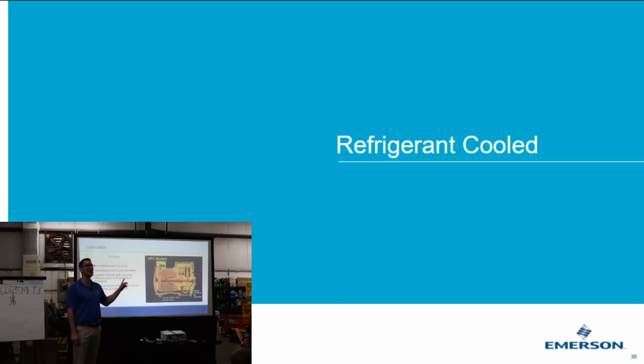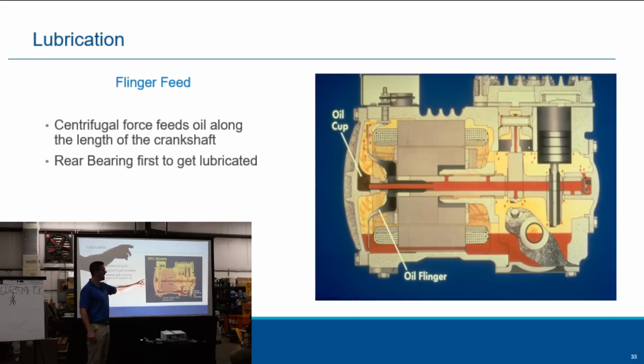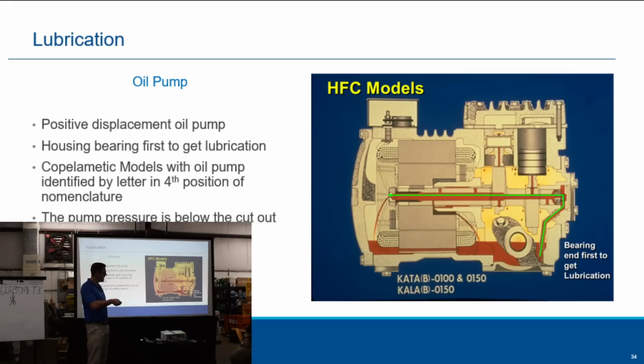What I've seen many times, because I've done tons of teardowns with some of the best compressor inspectors in the world, is they come back where the guys pull off the oil pump and yank on it, snap this little tube right here, and say, oh, it came from Copeland like that, ran for 6 months, but now all of a sudden the tube broke off. Well, no, we know that you pulled on it and snapped it. So just be aware of that. You might have to turn the pump and pull it out, or you might have to pull the bottom off. Best way is to pull the bottom off to take a look at it. If you break it, is a compressor going to run 6 months with no oil? No, it's going to seize, exactly.